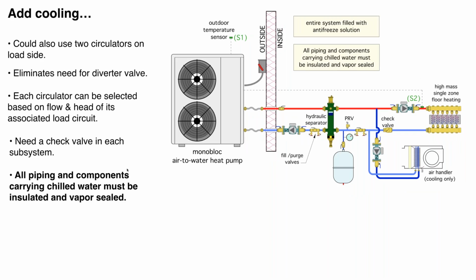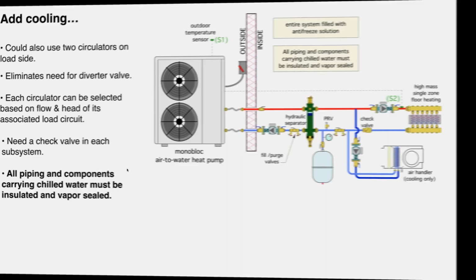So, excuse me, here's another configuration. All I've done here is use 2 different circulators, one for floor heating and the other for the air handler. The advantage of doing this is that if you have significant differences in flow rates or head losses, you can size each circulator for the flow and head requirement of its respective circuit, as opposed to a single circulator with a diverter valve. Okay, so that's another option.